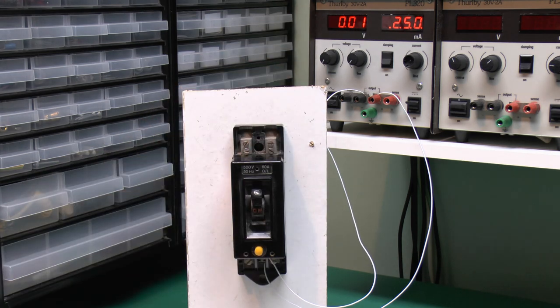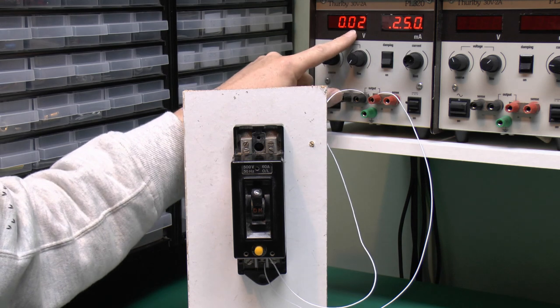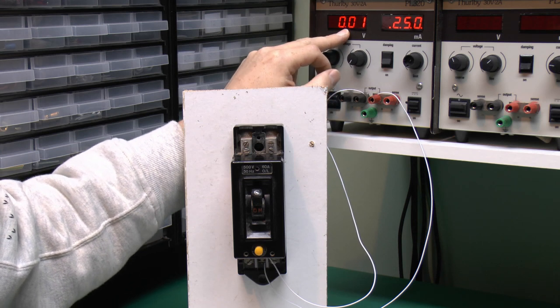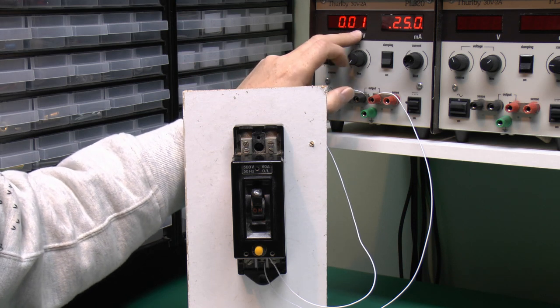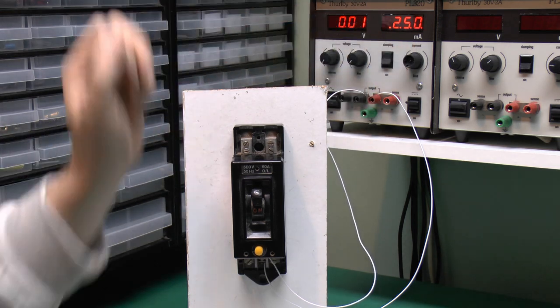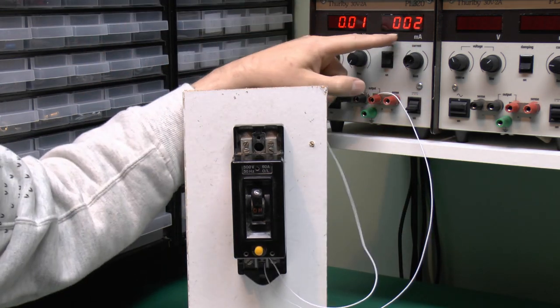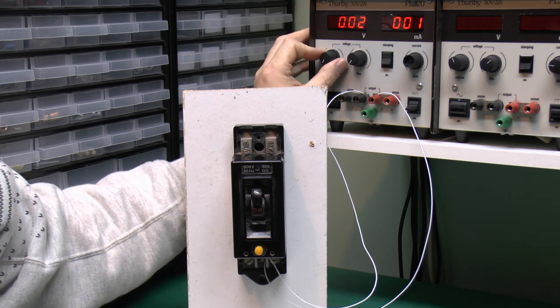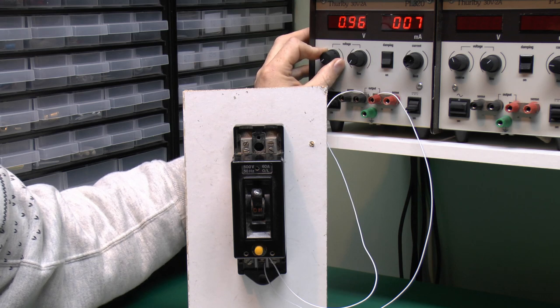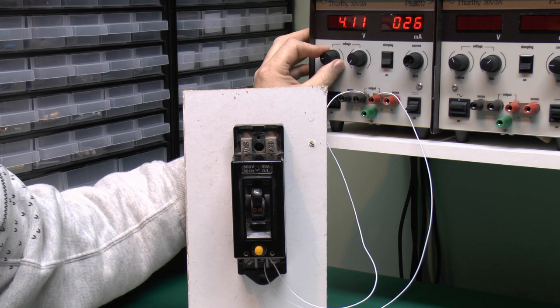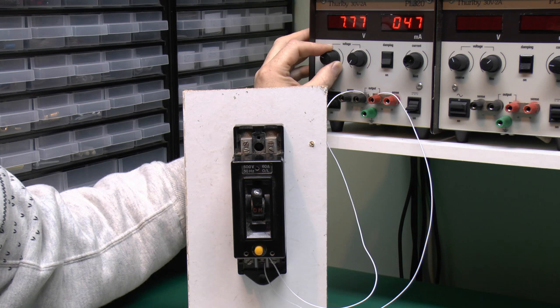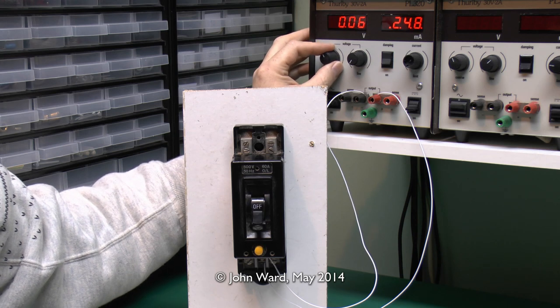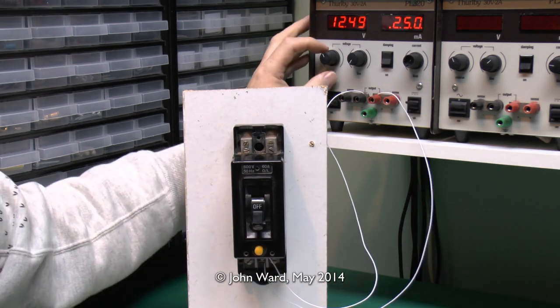Using this DC power supply, although it's DC, it's only a magnetic coil so it shouldn't make a great deal of difference. This is current limited so it won't blow up or set on fire when the thing does trip off. I'll set the current there to 25.0mA maximum, that should be more than plenty. Note that there is a decimal point there, so that might not be obvious on the video. So if we switch on and this will now display the actual current and this is the voltage we're applying. Alright, there we go then, so that tripped at about 12.5V there.